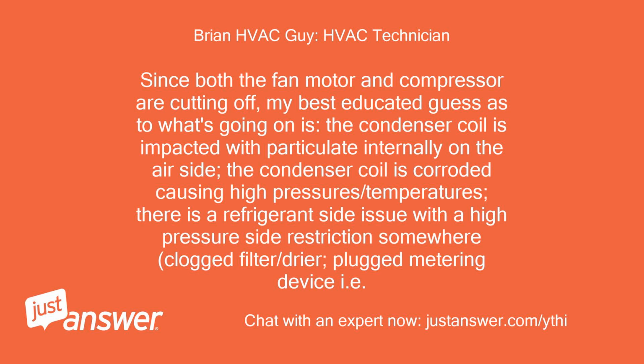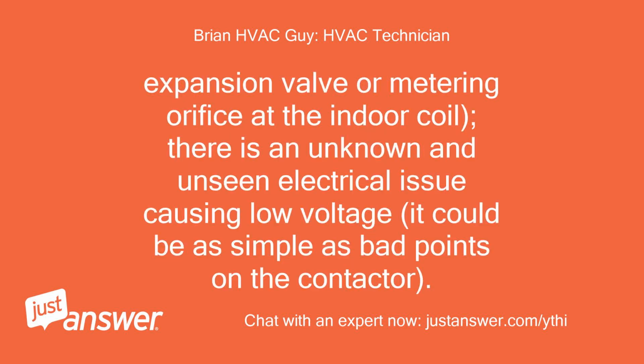Since both the fan motor and compressor are cutting off, my best educated guess as to what's going on is: the condenser coil is impacted with particulate internally on the air side. The condenser coil is corroded, causing high pressures/temperatures. There is a refrigerant side issue with a high pressure side restriction somewhere, clogged filter/dryer, plugged metering device, i.e. expansion valve or metering orifice at the indoor coil. There is an unknown and unseen electrical issue causing low voltage. It could be as simple as bad points on the contactor.